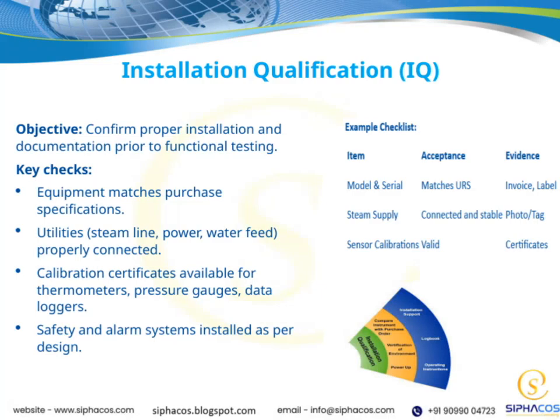Let's talk about Installation Qualification, or IQ. The main goal here is to make sure that everything has been installed correctly and that all the documentation is in place before we move on to functional testing. This step is crucial because it sets the foundation for everything that follows. First, we want to verify that the equipment matches the purchase specifications. This means double-checking that we've received the right equipment and that it conforms to what was ordered. It's about ensuring accuracy from the start.